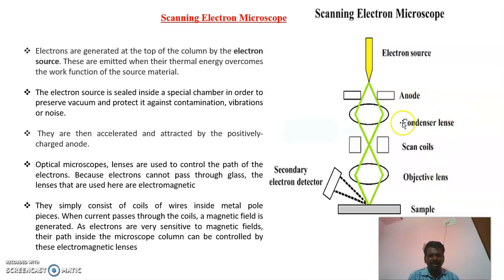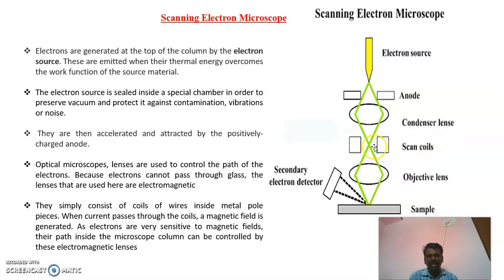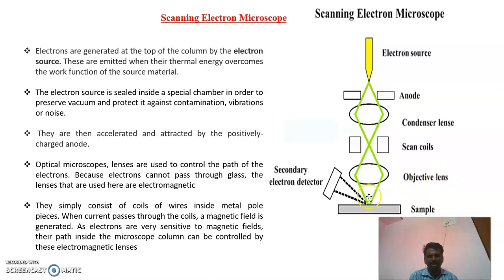These optical lenses consist of a condenser lens, coil lens, scan coils, and objective lens. Condenser lenses are used to control the size of the beam. Scan coils generate an electromagnetic field — that is, a magnetic field — which is more sensitive to the electrons. The objective lens focuses the electron beam on the sample.